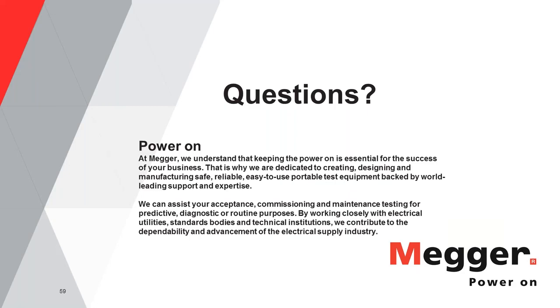The second part of the question is talking about, should you be performing the test at rated voltage and the current required to trip the breaker? That is what we call a factory test. Out in the field, you don't have the luxury of 6,000 amps at 480 volts. That's just going to be a huge amount of power source that you need to have. So typically, the test is performed at high current and less voltage.